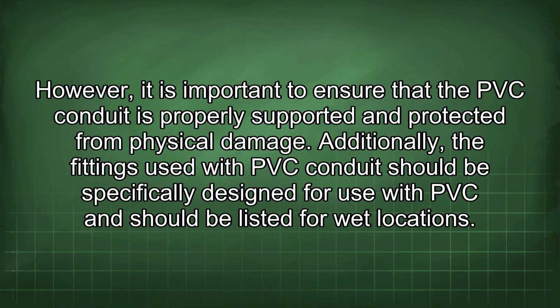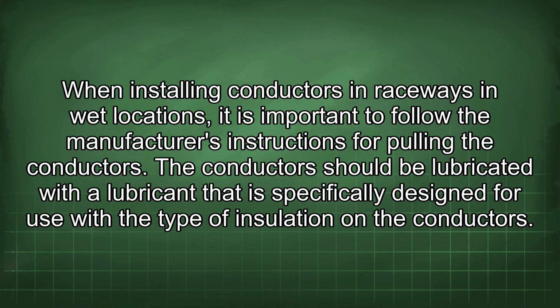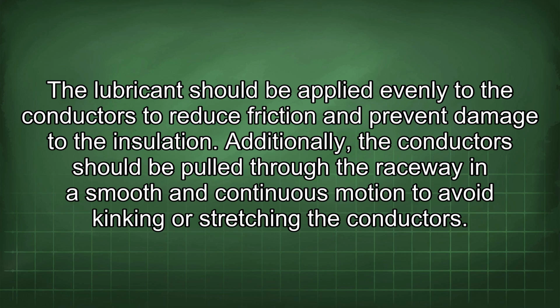listed for wet locations. When installing conductors in raceways in wet locations, it is important to follow the manufacturer's instructions for pulling the conductors. The conductors should be lubricated with a lubricant that is specifically designed for use with the type of insulation on the conductors. The lubricant should be applied evenly to the conductors to reduce friction and prevent damage to the insulation.